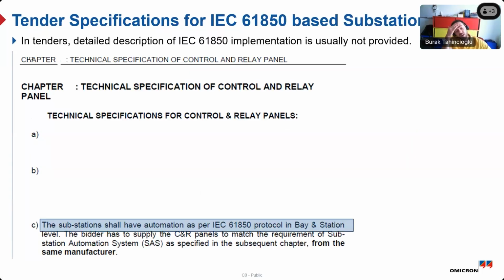But the experience until now was not so optimistic, because we have seen that tenders have a description of the 61850 implementation without details provided. It's basically saying in one sentence that the substation will be based on the 61850 protocol. That would not help us have full control over the project. That's why this is the initial point where we want to specify our substation before the tendering stage.